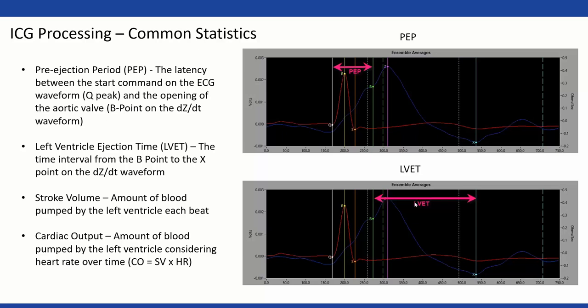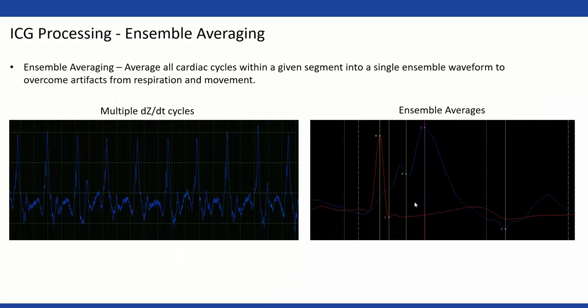With impedance, one thing we're going to do to make the data workable is take all of the individual cycles — shown here in blue — and average them all together into one ensemble average. This helps a lot with any movement artifact or respiration that might be affecting individual cycles. Going through every single cycle to edit would be very tedious, so this is a way to get the same information averaged together, where small changes are less important but the result is still powerful.